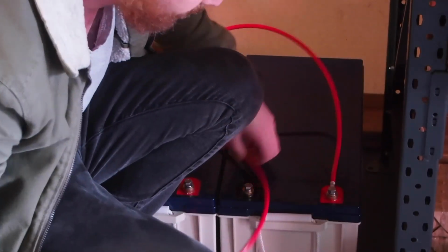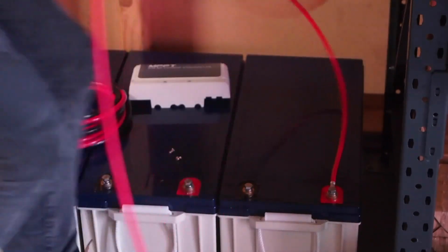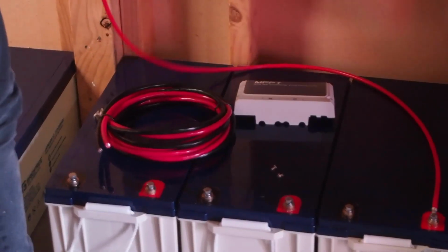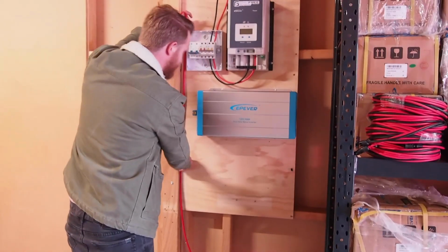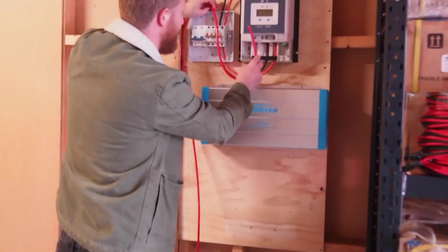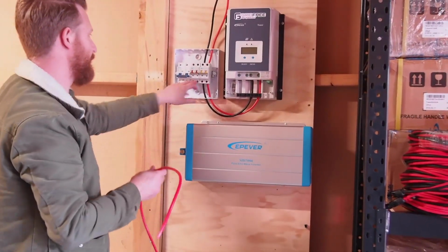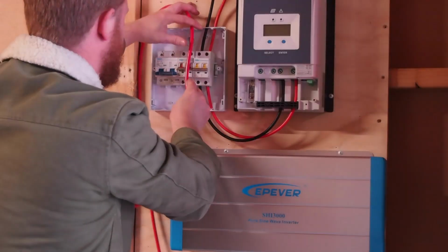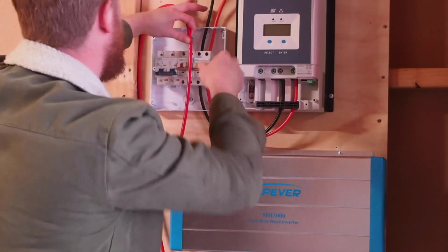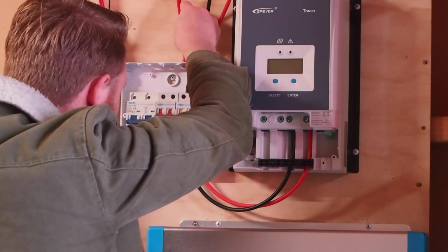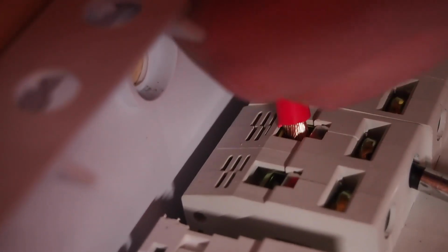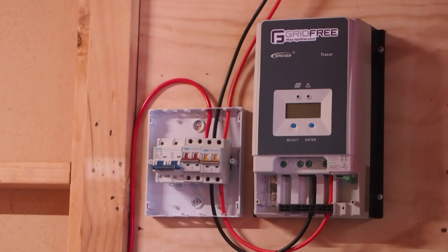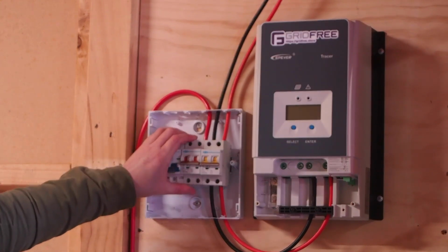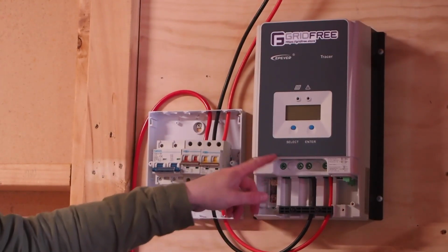So to make sure we get this cable as tidy as possible, I like to screw down the positive side first, and then we make our cable run up to the circuit breaker. Now, you want to make sure you've got enough cable to go all the way into the charge controller, because we're going to use this cable to make the run from here into here as well. So now we've got our positive run that goes into this circuit breaker, and then we want to do a positive run from the circuit breaker into the charge controller.